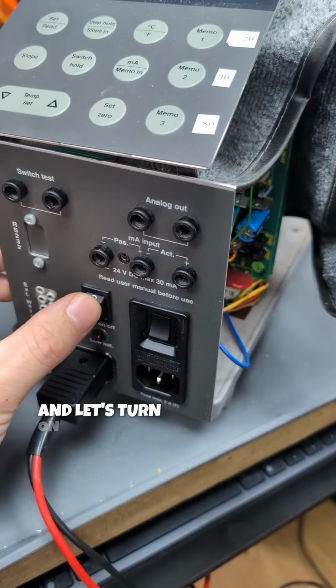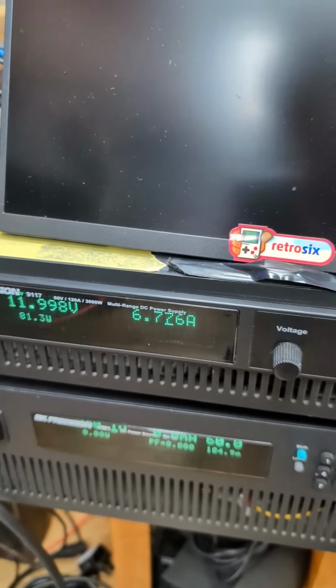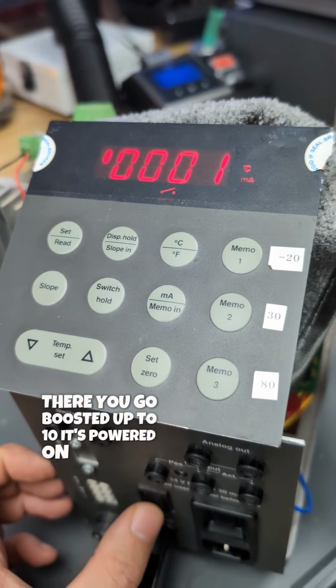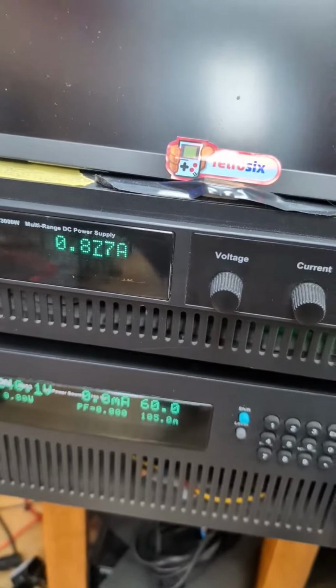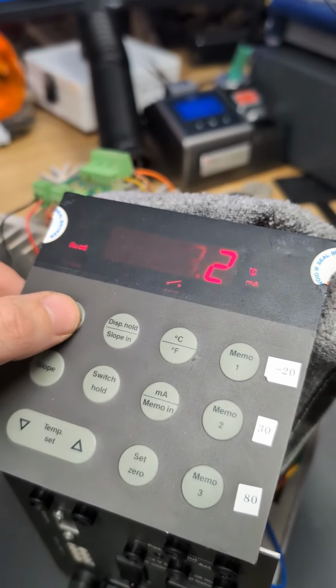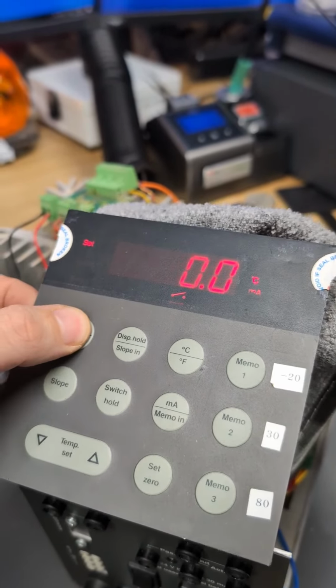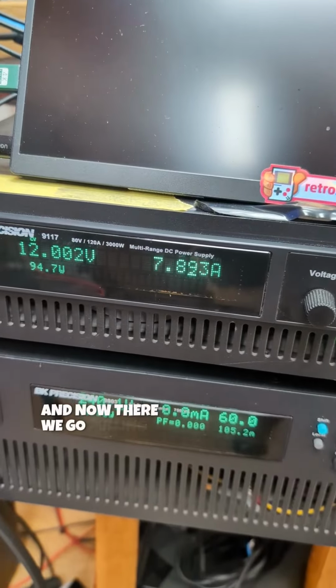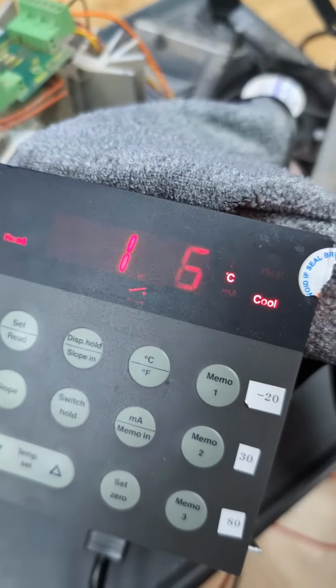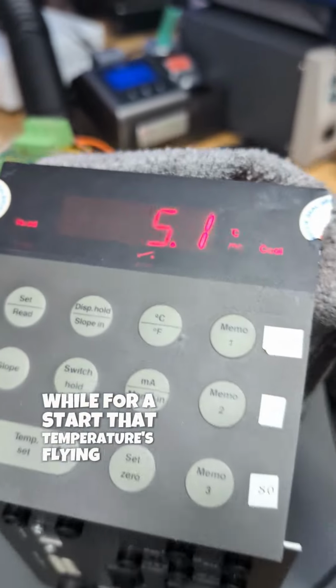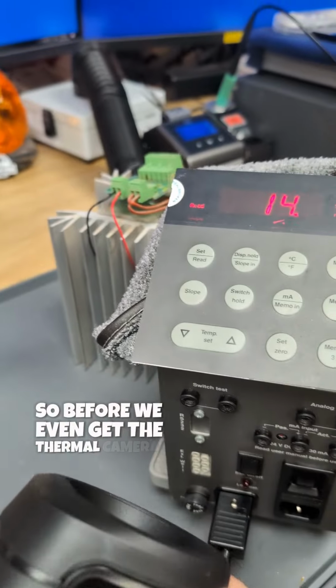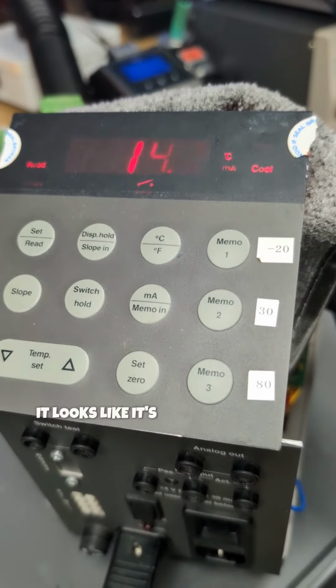And let's turn on and monitor the current. There you go, boosted up to 10. It's powered on. So it's drawing the same 0.9 amps at the minute. Let's set it to cool. And now, there we go, pulling 8 amps. So let's inspect this with a thermal camera. Well, for a start, that temperature's flying down. So before we even get the thermal camera on, it looks like it's working.